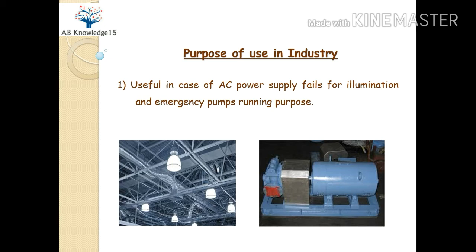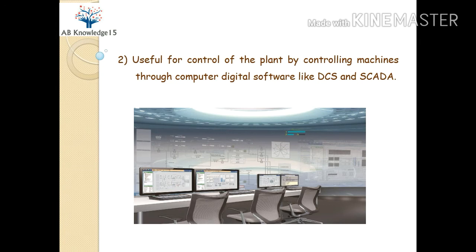Next is the purpose of use of the battery bank in industry. The first purpose is useful for illumination and running emergency pump motors. Suppose AC power fails in any industry — there will be a blackout. But if battery banks are installed in the plant, DC power comes into line and the necessary parts will be illuminated by the DC power source through the battery bank. For emergency pump running motors — such as lubrication motors, oil jacking motors, and seal oil motors — power will be provided by the battery bank.